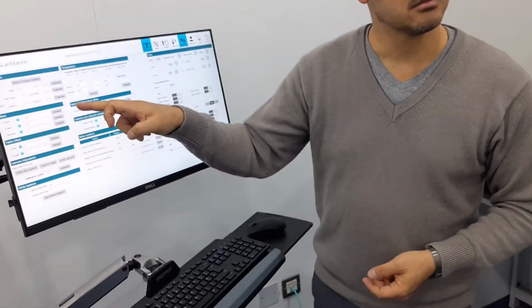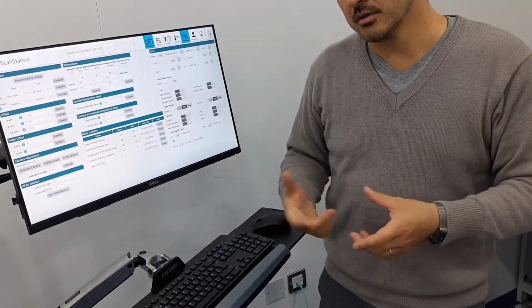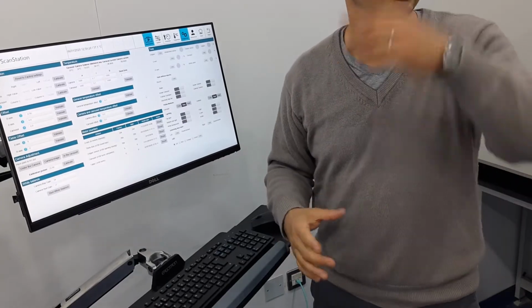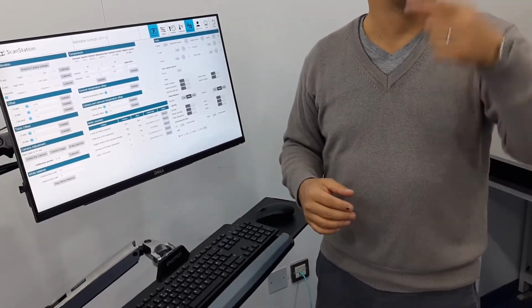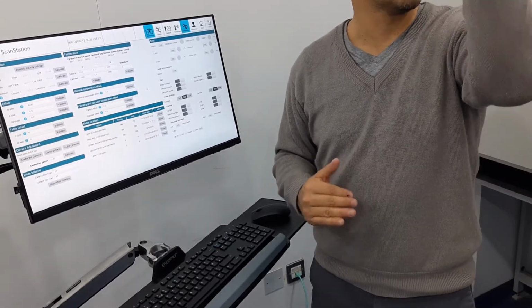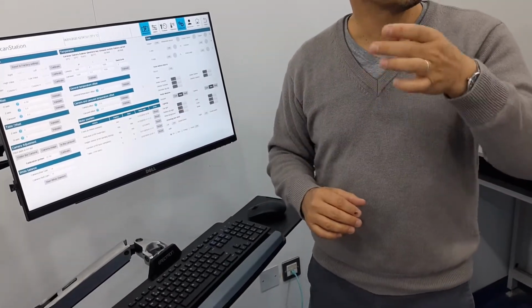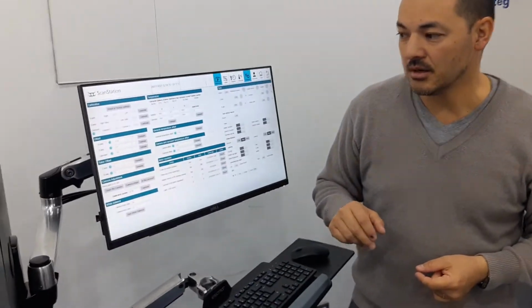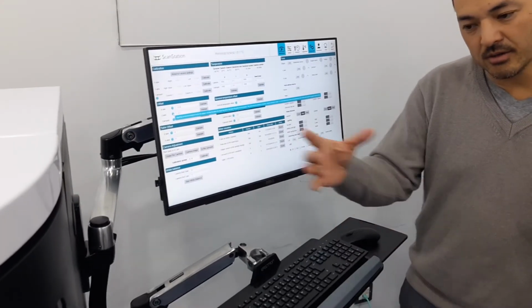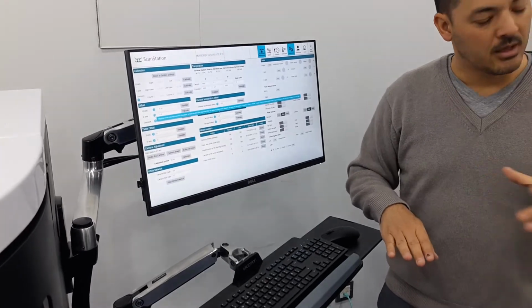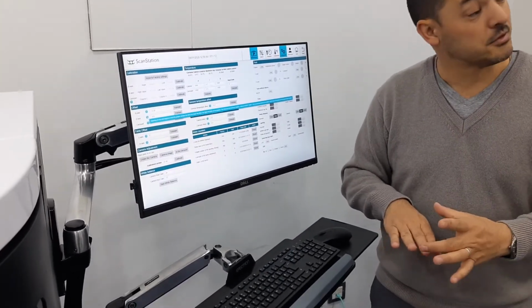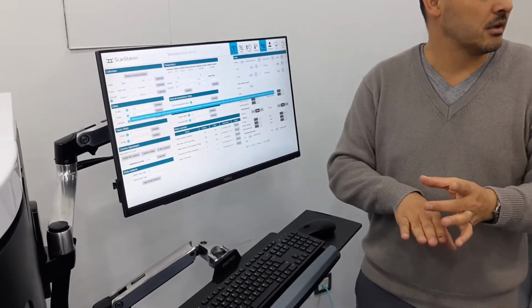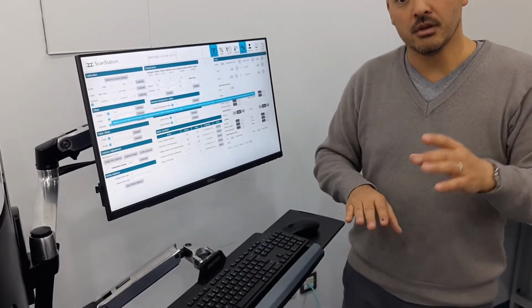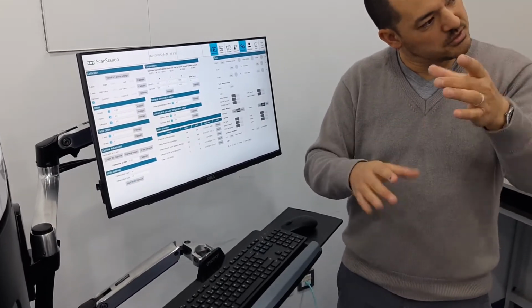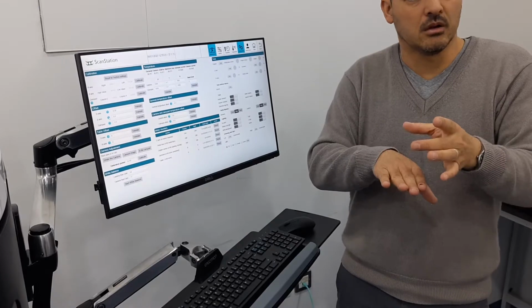Then after there's the offsets. But the calibration, if you push calibrate, the robot will move until the mechanical stoppers, and it will calibrate the values of the sensor against the mechanical stoppers. And then after you have an offset. For example, the Z-axis, so here the same thing, there's some explanations, but the carousel petals are a certain height, and then the gripper will go at a certain height too, and it needs to be a bit above, but not too high. So if it's a bit too high, you can offset and diminish the height, or you can make it a little bit bigger.